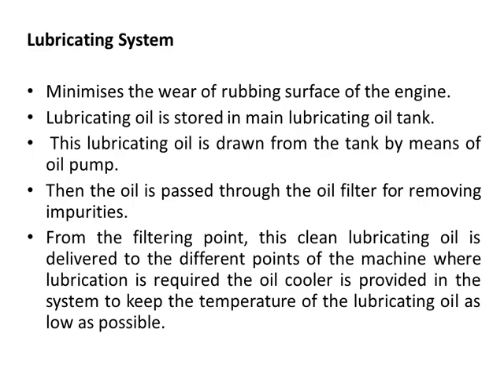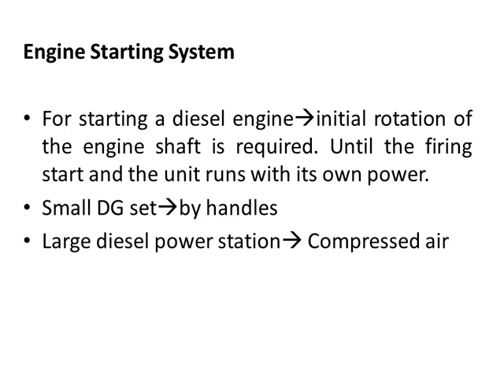The engine starting system: small diesel power stations can be started manually, but large diesel generating sets cannot be started by manual methods. In that case, compressed air is used for starting. For starting a diesel engine, an initial rotation of the engine shaft is required until firing starts and the unit runs on its own power. For small DG sets, this initial rotation is provided by handles manually, but for larger diesel power stations, compressed air is used.